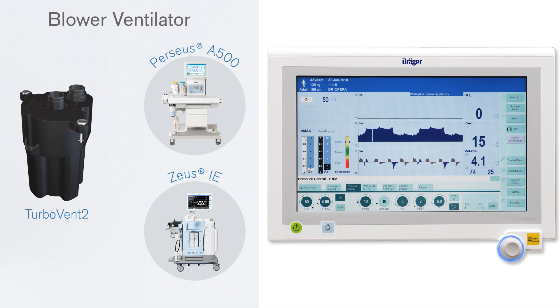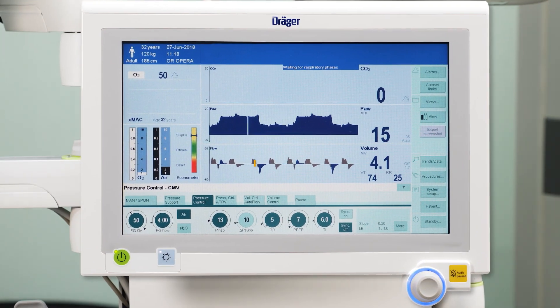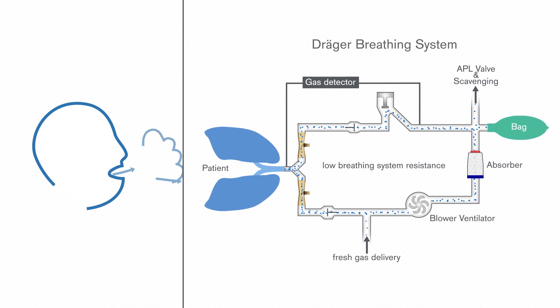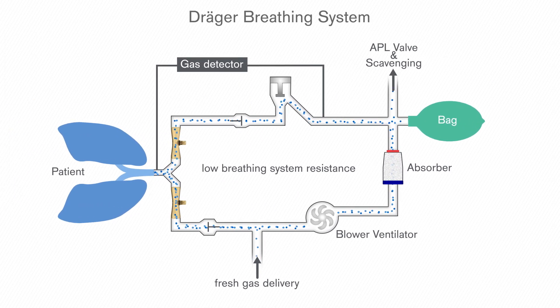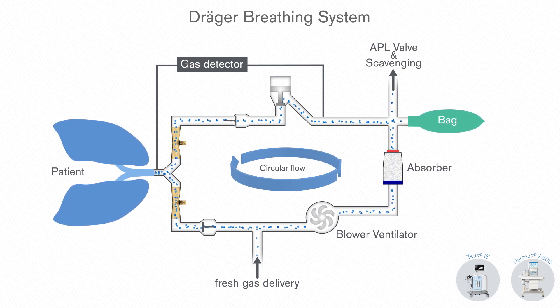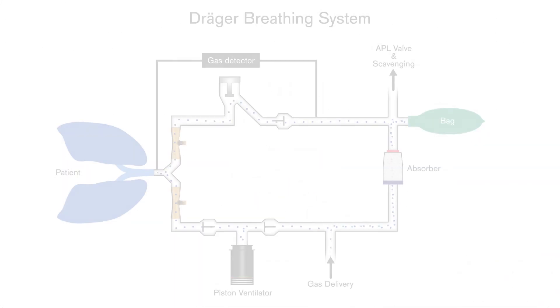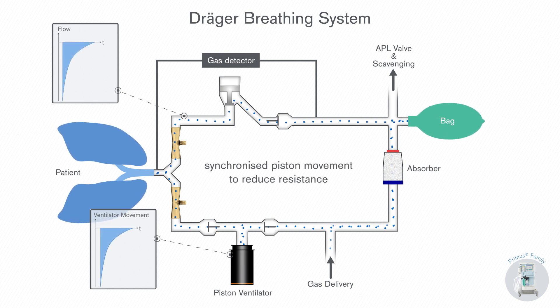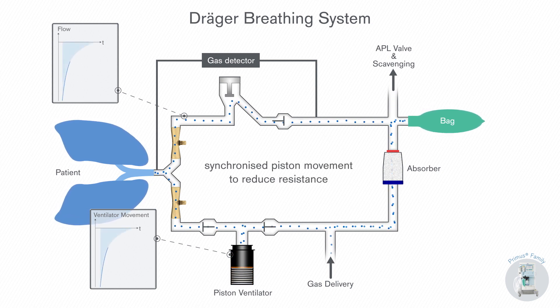The blower ventilator of Zeus IE and Perseus A500 allows spontaneous breathing at all times and in all pressure modes, independent of the activation of synchronization, even during the inspiratory phase and at PEEP level, like a real BiPAP. In order to make spontaneous breathing easier, the breathing system resistance should be as low as possible. The blower ventilator of the Zeus IE and the Perseus A500 generates a minimal circular flow which continuously circulates in the breathing system to mitigate its resistance. The piston ventilator of Primus family devices synchronizes its movement during expiration with the patient's expiration and so reduces the resistance.